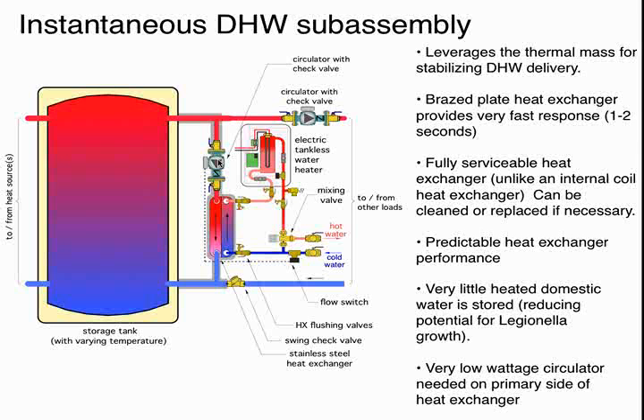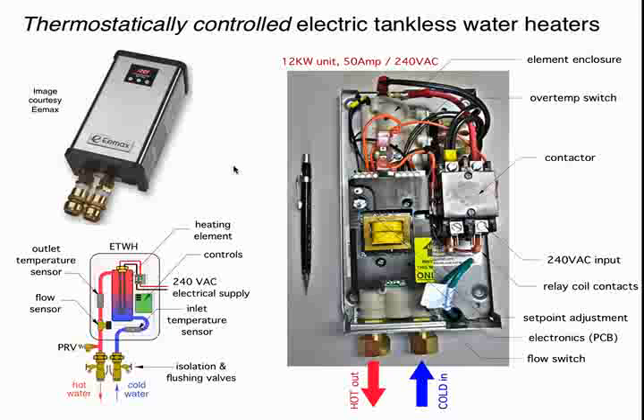Okay? And somebody asked, well, what about the power requirement to run the circulator? We actually did a scenario on that. For a typical family of 4, we found that that circulator will run for less than $1 per year. So it's an incidental cost for operating that circulator. Remember, that circulator only operates when there is an actual demand for domestic hot water. And this is a small circulator in a residential application. A 30 to 40 watt circulator would work there.